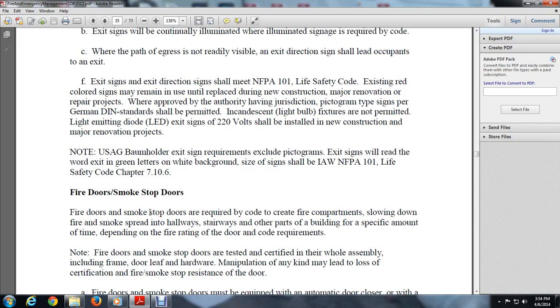Smoke stop doors are required to create a fire compartment and slow down fire and smoke spread to the hallways, stairways, and other parts of the building for a specific amount of time, depending on the fire rating of the door and code requirements. Note that fire doors, smoke doors, or smoke stop doors are tested and certified as a whole assembly, including the frame, door leaf, and hardware. Any manipulation of the assembly may lead to the loss of certification and of the fire and smoke resistance of the doors.